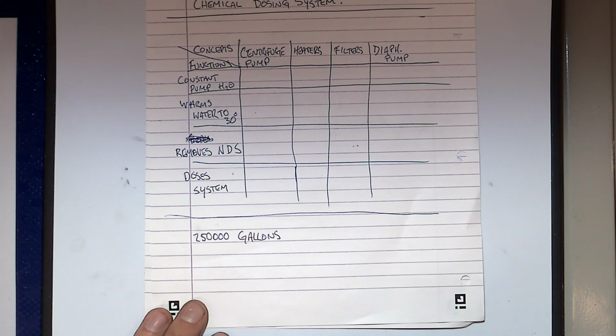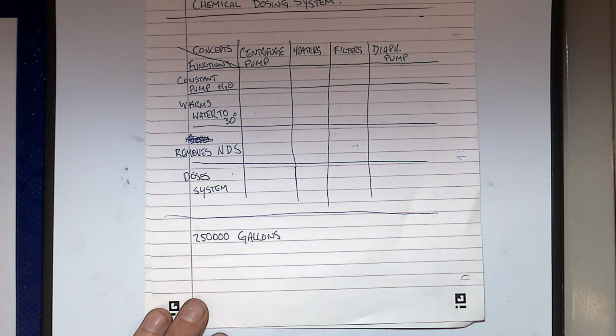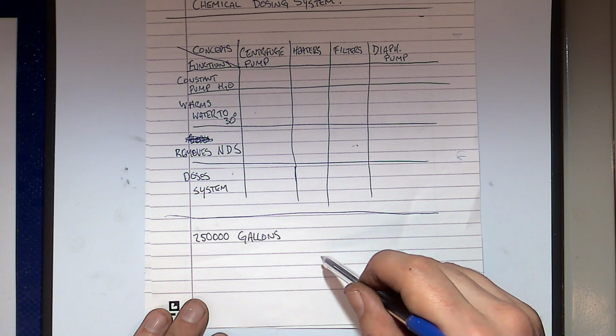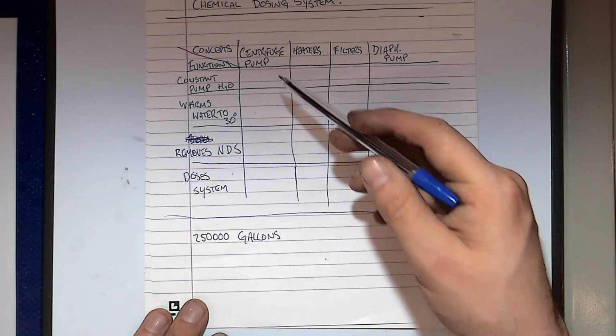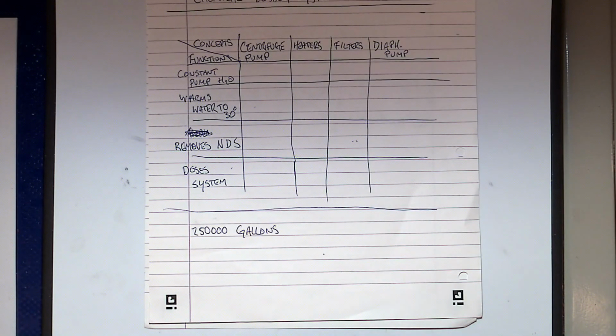Again, your filters have to handle that volume of liquid, and your diaphragm pump needs to be strong enough to dose at a level that is going to, dilute's not the right word, get your chlorine level to sufficient. So yeah, that's where your maths comes in at the end there. And then we can insert specific concepts. So my centrifuge pump is going to be model X that pumps at the rate Y. My heaters are going to be able to heat P amount of water to Q temperature. Filters are going to be able to filter said amount of water, and yeah, your pump's going to be able to dose enough into that system.